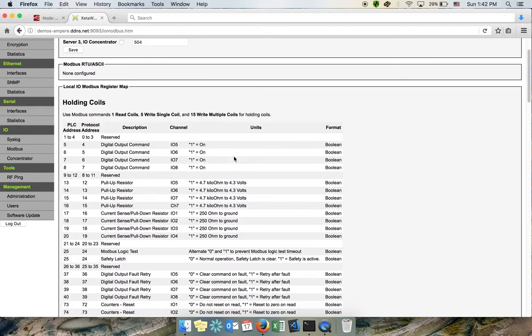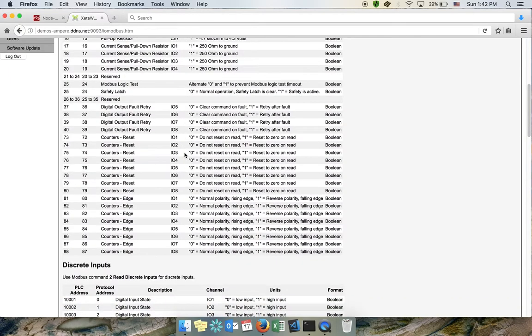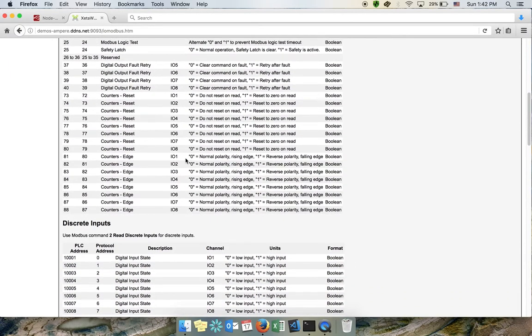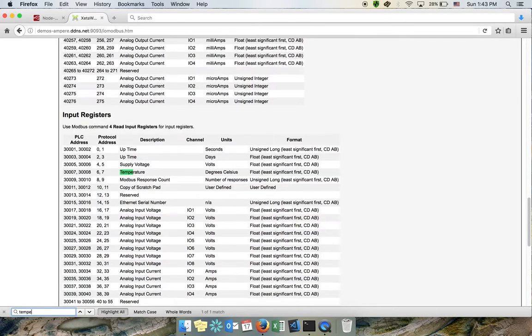Look for the temperature in the specification sheet. If you find it hard to understand, you can simply search for 'temperature' in the document. Some devices have default values like supply voltage or temperature, so you can read what those values are on the device or gateway you are using with Modbus. In this case, temperature is located at addresses 6 and 7.